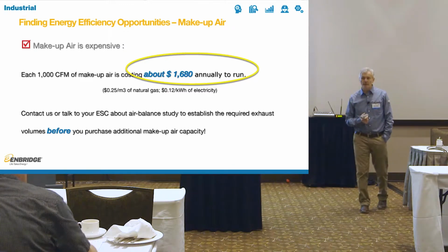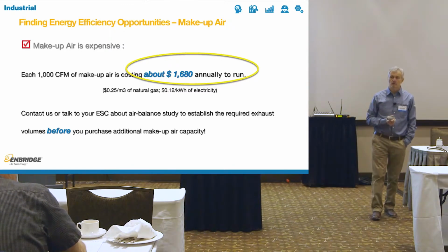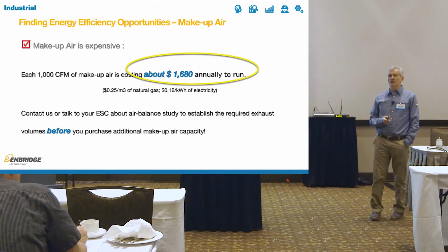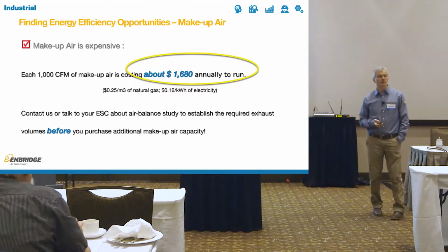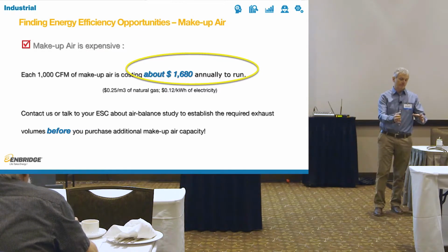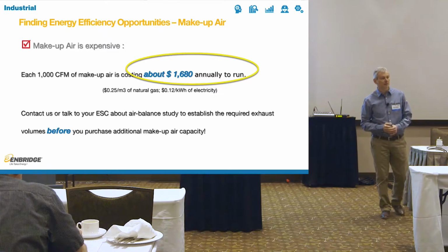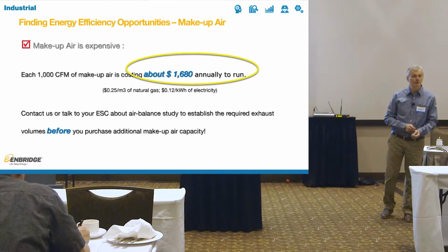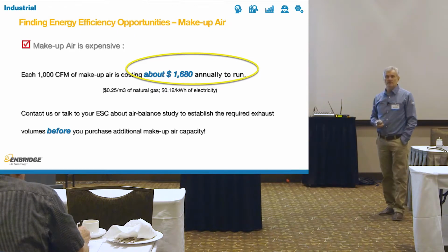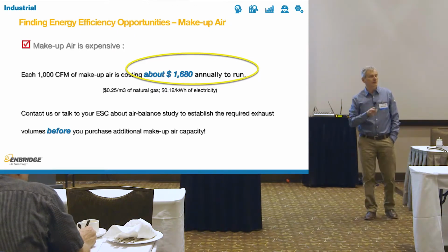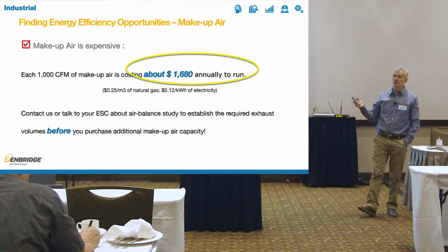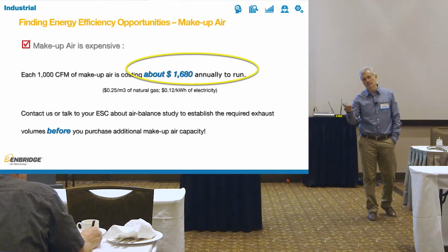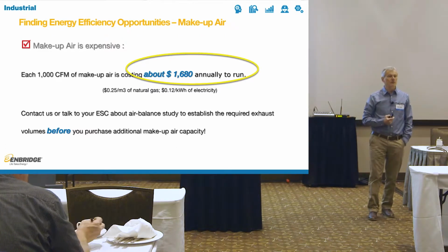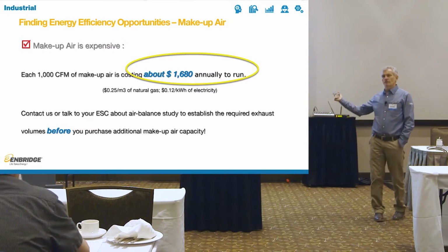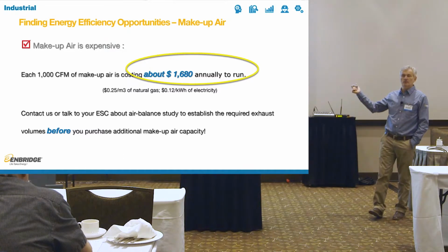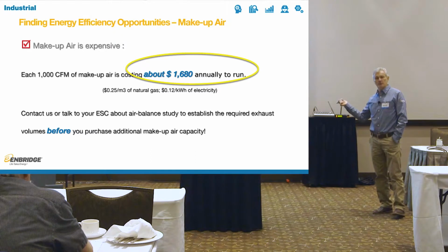Each 1,000 CFM of makeup air costs you about $1,700. How many of you have installed anything that's only 1,000 CFM recently in your facility? Even those tiny little roof fans are 5,000, 10,000, 20,000 CFM. So multiply that by 10, that's $16,000. Every 10,000 CFM, $16,000 in money. So when somebody says, oh, you're a little negative, I'll put another 50,000 CFM makeup air unit on your roof, that's 50 times $1,680 every year that you will be paying for that privilege.